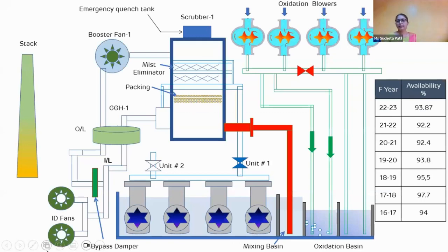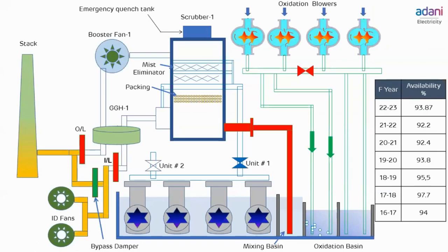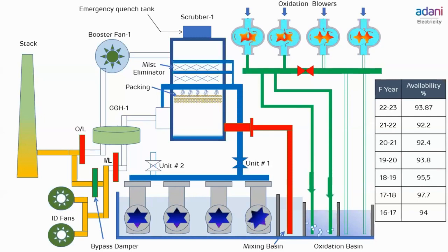This is the flow diagram of FGD at Adani Dahanu Thermal Power Station. Before installation of FGD, the flue gas from boiler was directly discharged through the stack. But now we have FGD. The flue gas desulfurization system is accomplished by seawater scrubbing, and each stream of 250 megawatt line has an independent stand-alone seawater scrubbing system. Each scrubber is designed for around 10 lakh normal meter cube per hour of flue gas flow from boiler, and the removal efficiency of SO2 is more than 90%.